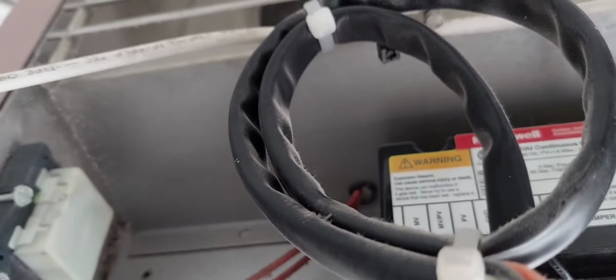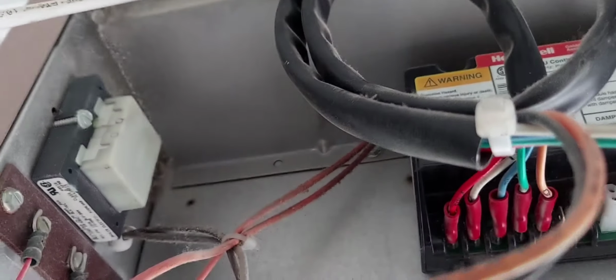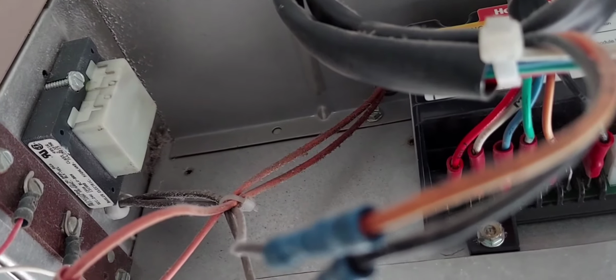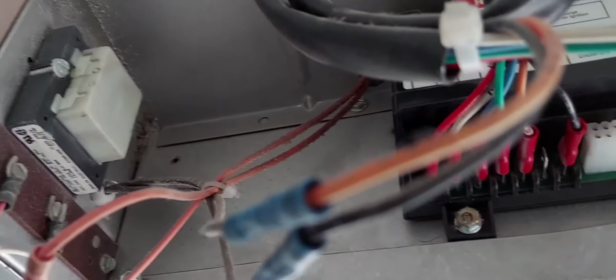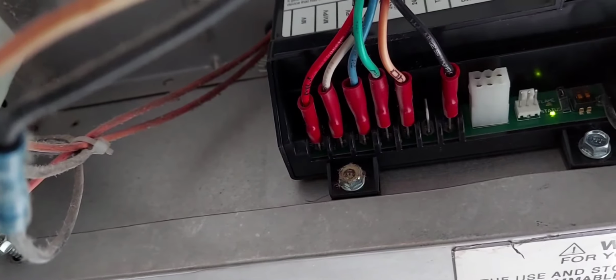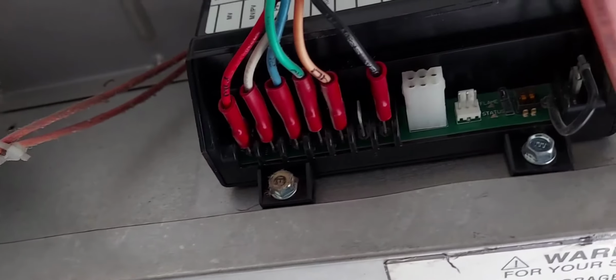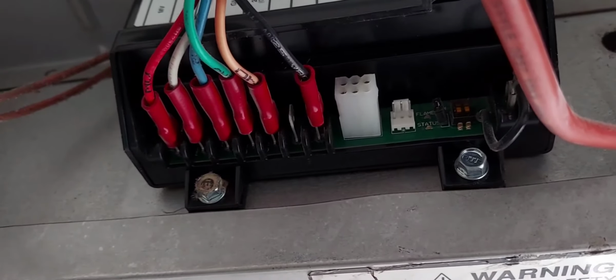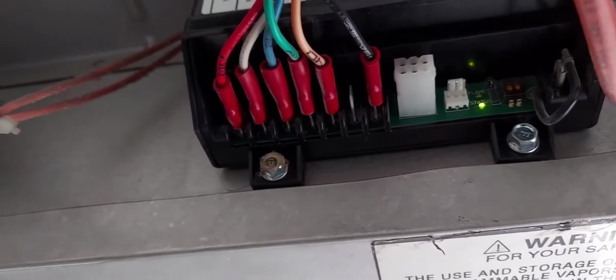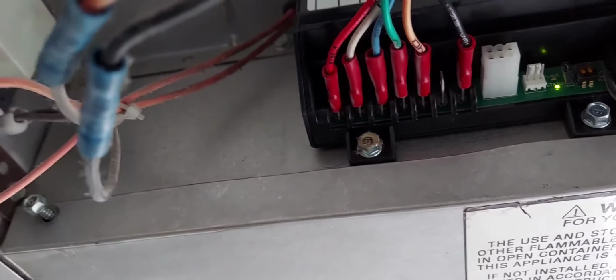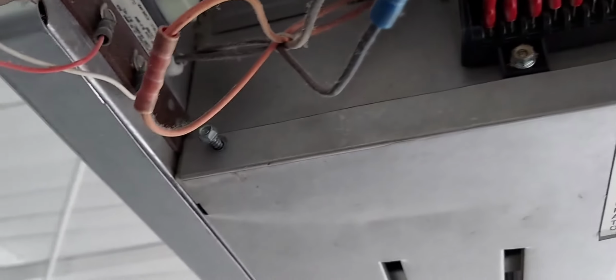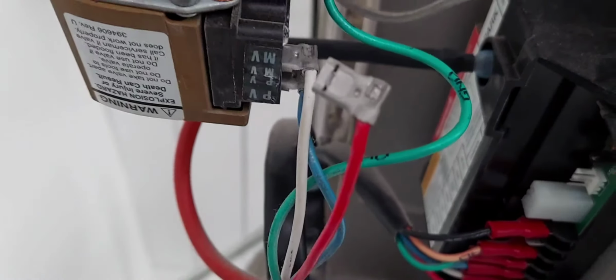Okay, so it's going to be either a gas valve issue. If not the gas valve, if the gas valve is good, then we're going to have to look into the flame sensor. But based on experience, I would say more than likely the flame sensor is the issue. So I'm going to open up the furnace right here, over the bottom, a couple screws right here, get it open and get in there. Stay tuned.